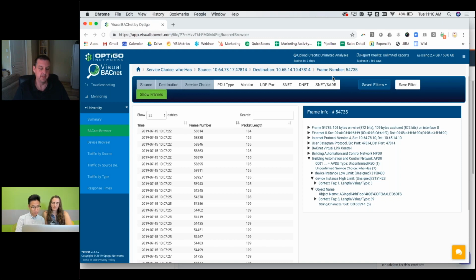And this is almost a fault in tagging. If you're looking for the wrong tag that doesn't exist, then you wouldn't be able to find it. So I would double check what it's looking for against what you actually have on your BMS system to see if it correlates. If it doesn't, then you're going to have to change what that reference is so that you can find it easily.